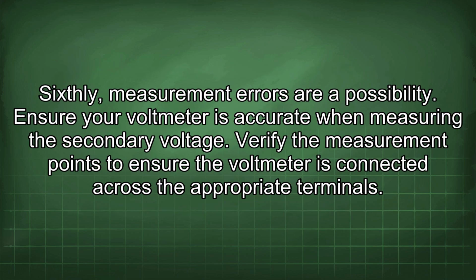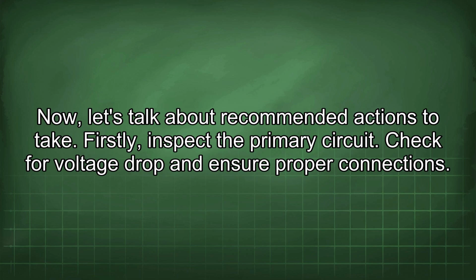Sixthly, measurement errors are a possibility. Ensure your voltmeter is accurate when measuring the secondary voltage. Verify the measurement points to ensure the voltmeter is connected across the appropriate terminals. Now, let's talk about recommended actions to take.